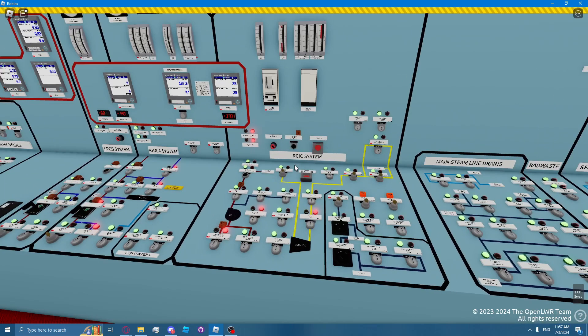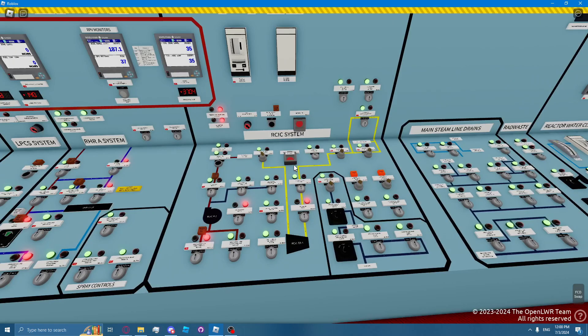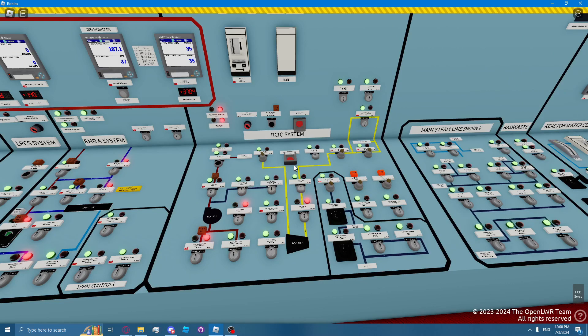The RCIC turbine trips when the system isolates. The RCIC system isolation signal can be reset and bypassed by placing both isolation signal seal-ins to bypass.